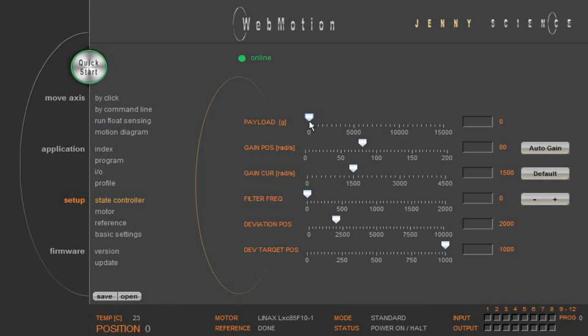Another adjustment you can do manually is the fine tuning. As we have seen before, with Gain Position, you can change the position stiffness. Higher values result in higher precision, but there is a tendency of oscillation and more noise.